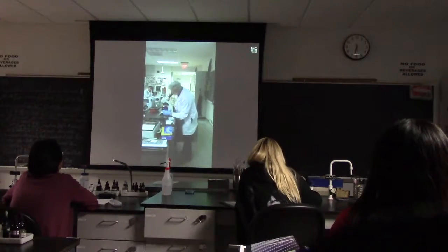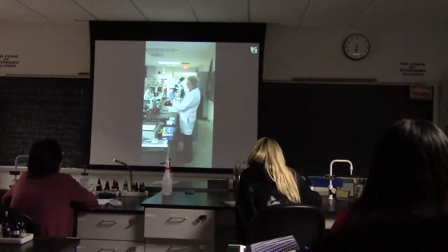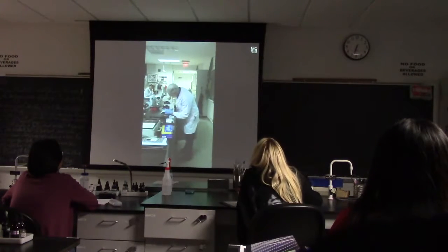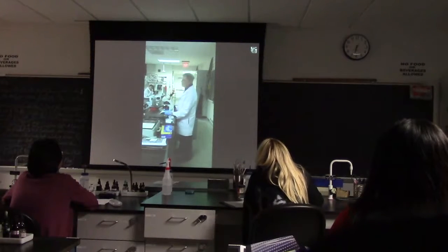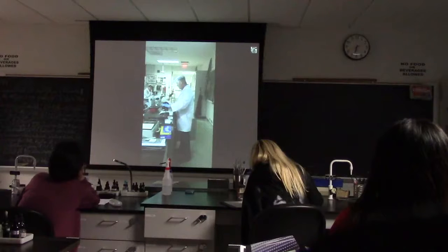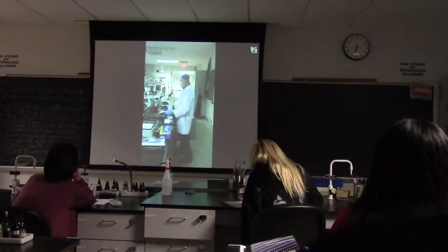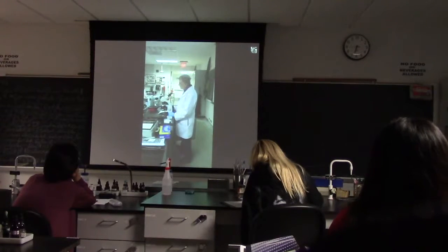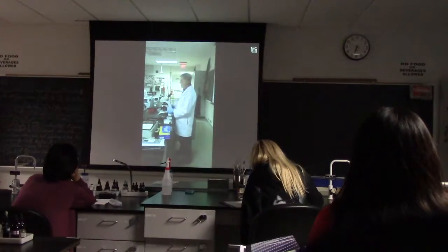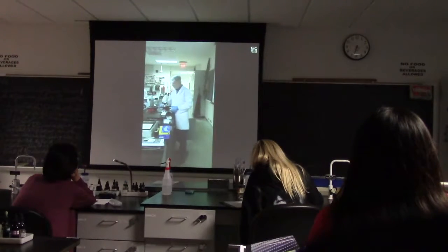Alright? Then you're going to use these stage control knobs beneath the stage on the left side. You're going to orient the colored portion of the slide that you want to look at directly over the condenser light. Make sure it's not pushing up through the slide, just almost touching. Then click the 10x into place, and bring the stage with the coarse adjustment all the way up.